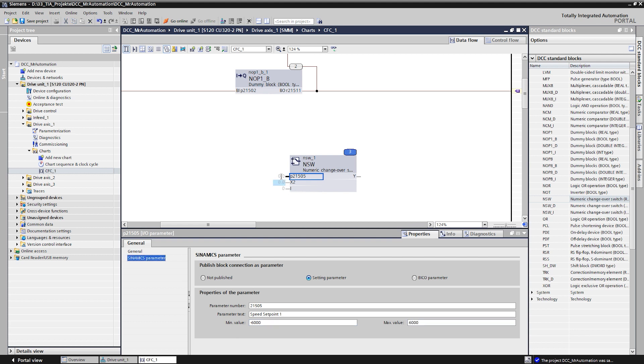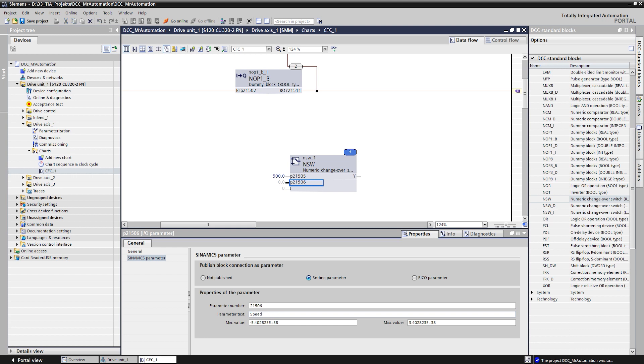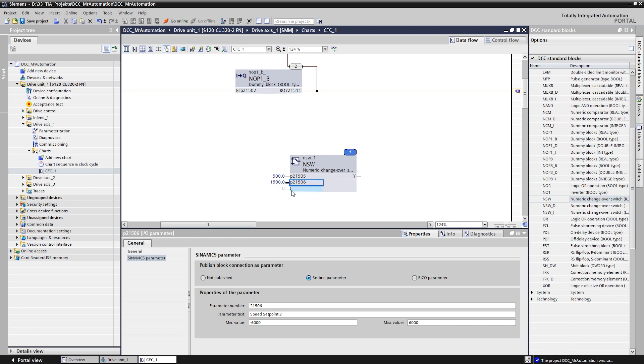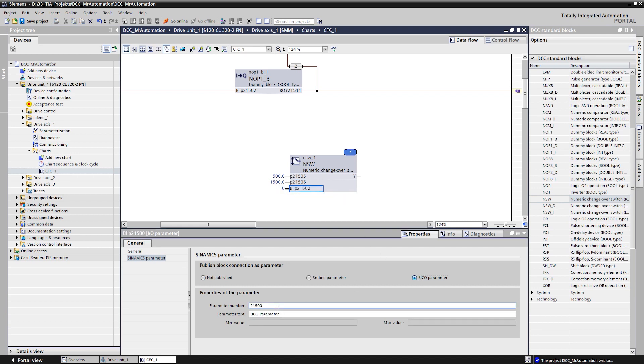The default values for the speeds are set to 500 and 1500. These values can of course also be changed later during operation via the parameter list of the axis. The third input is used for switching between the two values. We publish this again as BICO parameter and connect it to the third digital input of the control unit.